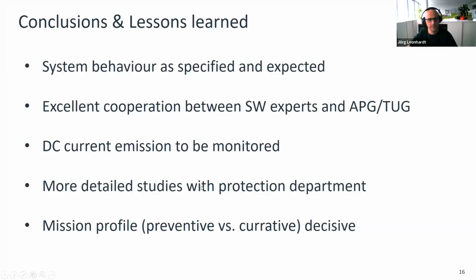You need to do more detailed studies with the protection department. This depends very much on the mission profile you want to drive with such a load flow controlling device. It depends if you want to operate them in a preventive mode, which means you inject permanently and change the impedance of the line, or if you want to operate them in a curative mode, that means only in case of a failure in the grid. So this is decisive. So these are some lessons learned, what is impacting what you need to do if you want to include such a system in your system. So thank you so far.